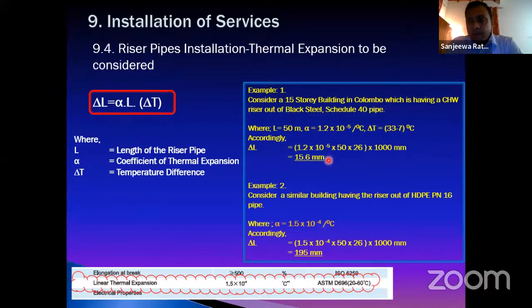So there are thermal expansion joints. In many projects I have noticed that sometimes the consultants and the contractors have no proper idea of thermal expansion for pipes. So consider example number 2, the same building with HDPE, that means high density polyethylene material, because nowadays HDPE pipes are very popular in the HVAC industry also. If you use HDPE pipe for the same riser, the linear thermal expansion is 195 millimeters. That's a huge value compared to the steel pipe, almost 9 times higher.